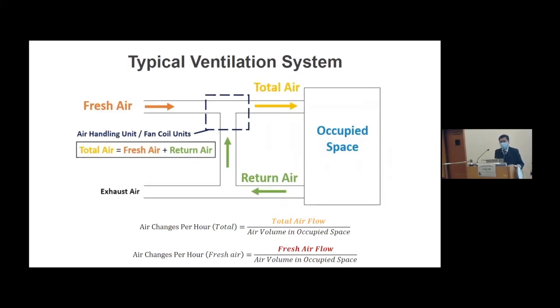In a typical ventilation system, fresh air is drawn from outdoors by either an air handling unit or fan coil units. The return air mixed with the fresh air is then conditioned to the desired temperature and relative humidity and supplied to the occupied space. At the bottom of the slide are two equations showing the definition of two different air changes per hour, namely the total air change and the fresh air change. It is important not to mix up the ACH of fresh air and the total ACH of the room, which have different meanings and requirements in the regulations and standards.